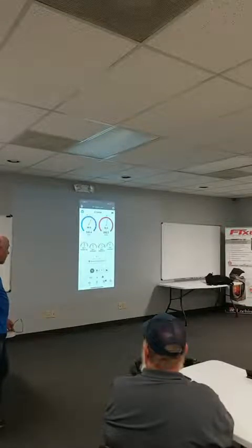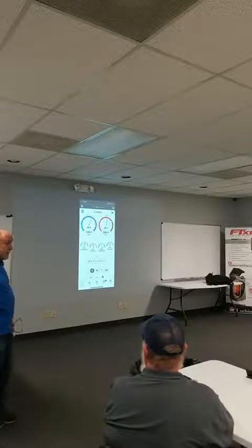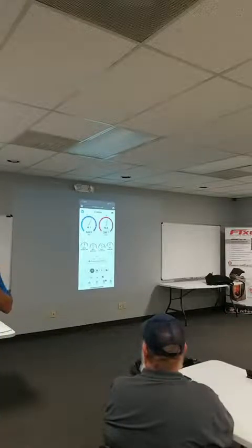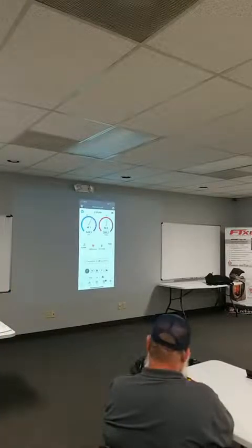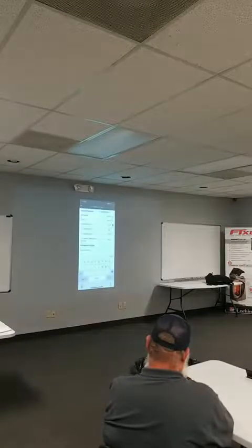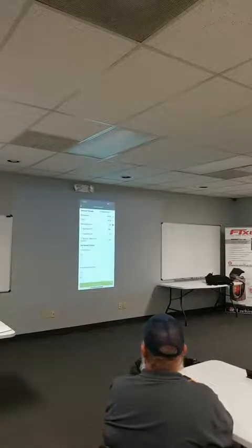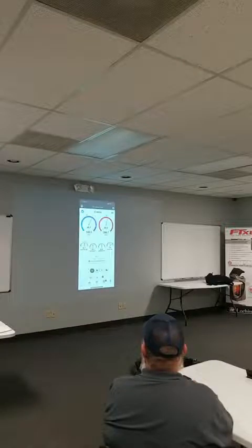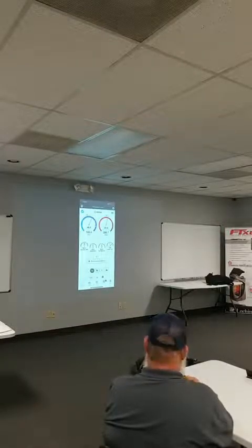One of the reasons, if you weigh the charge back in, I'd be real curious to see what Trane calls for in that unit. If you weigh it in and that's what it is, that's what it is. You benchmark the system at that. It's as simple as going into the profile, going into system info, and telling it that my target subcooling is not 10, it's 20. I hit done, and now the subcooling issue is gone, right? It's just that Measurequick is using that, but it's got a high liquid line temperature on there because it's higher than it should be.